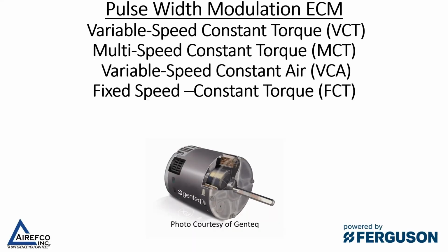Over the years, we've had numerous different pulse width modulation ECM motors. We've had the variable speed constant torque, VCT, the multi-speed constant torque, MCT, the variable speed constant air, VCA, and the fixed speed constant torque, FCT. There are troubleshooting guides that are available for all of these motors, because when you're troubleshooting the ECM motor, you need to know what kind of voltage you're going to see on the communication lines to the motors.